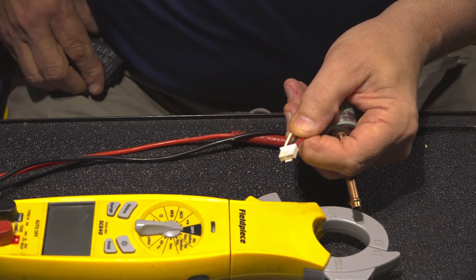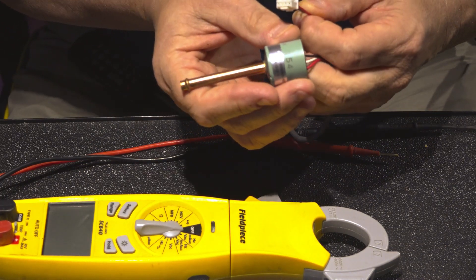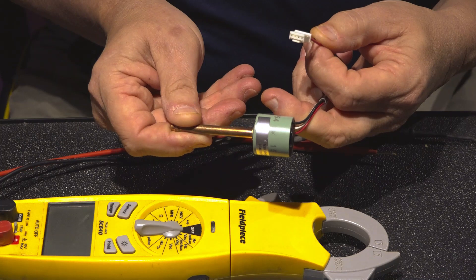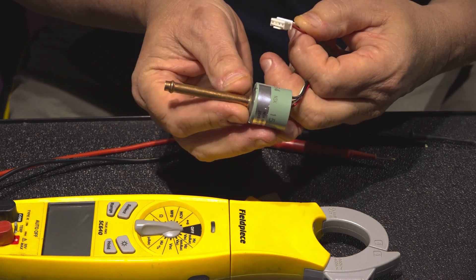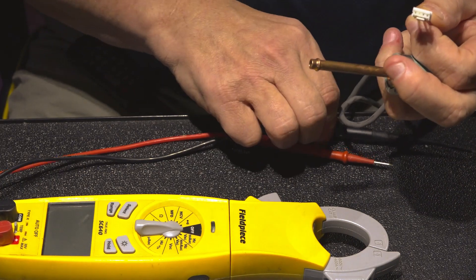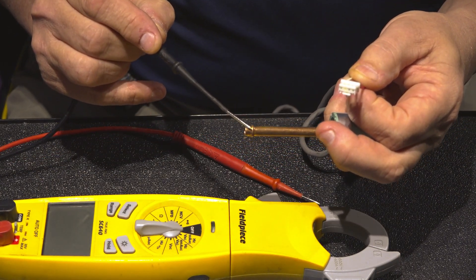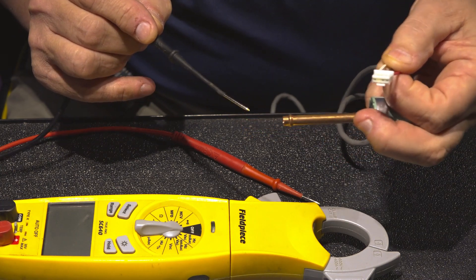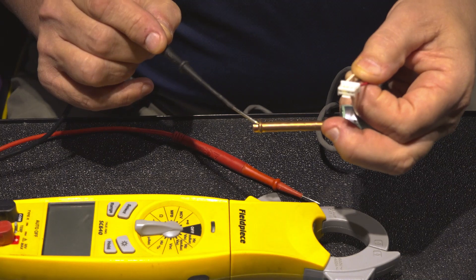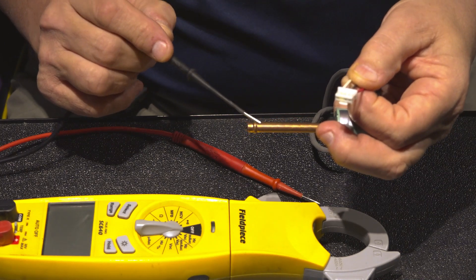Here's the pressure transducer that's used on all of the Amana and Daikin systems. A lot of our big VRF systems use these as well. It's going to be a sweat-in part. It's going to have a little collar here formed into the copper. So when you're sweating this thing in, you don't want to push it down past this little seal here, this little collar, so we don't create a restriction inside the line set itself.